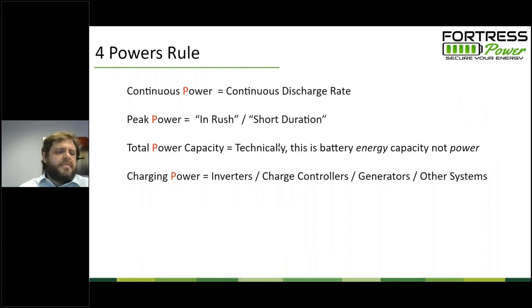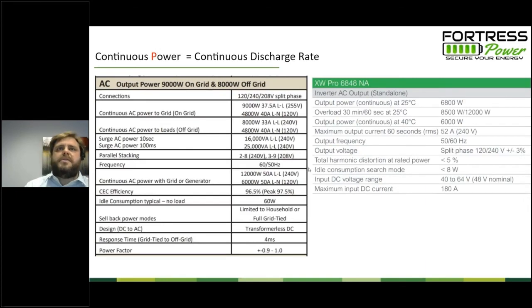Just diving right in, we have this training called the 4 powers rule, and I would say this is not something you need to memorize or write down, but it's more to ask yourself, when I am sizing a battery system, what size considerations do I need to be aware of? And of course, continuous output power is the number one thing. You buy an 8 kilowatt inverter, it has 8 kilowatts of output power, but then you also want to make sure you have enough juice in your tank, a large enough battery capacity. You also want to make sure that the system is well designed for maybe some electrical currents that you don't know about. And so we're going to talk about that issue as well as some charging issues to enhance our knowledge of battery sizing. So with that, let's dive right into some spec sheets.